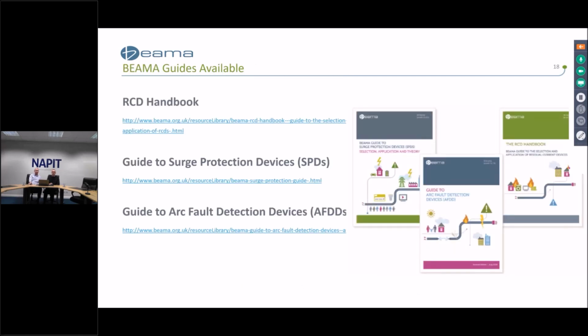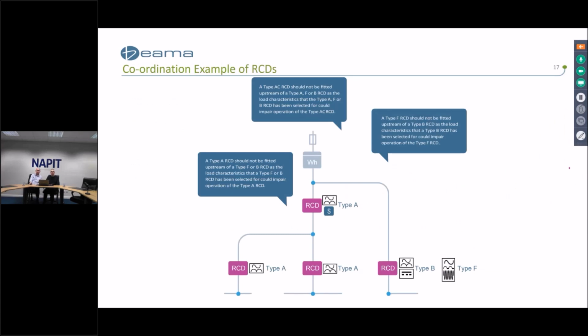Sorry, can we just go back? Just to mention also that where there are two RCDs in series, as we have in this middle leg, selectivity must also be applied. So you would still need a time delay or S-type RCD, and a 3 times residual current rating on the upstream device. Okay, sorry.